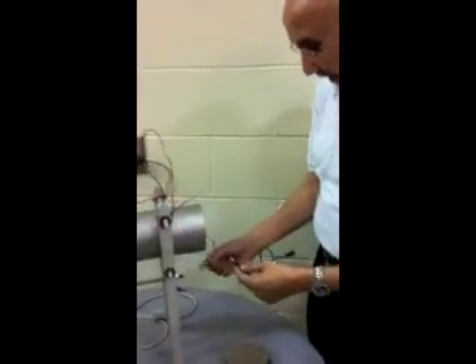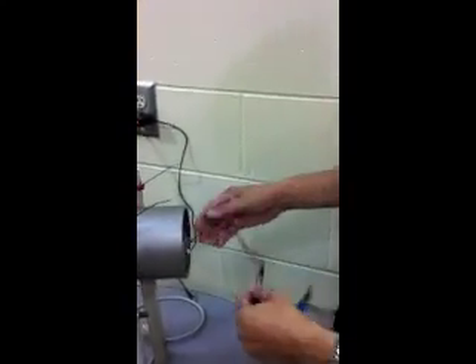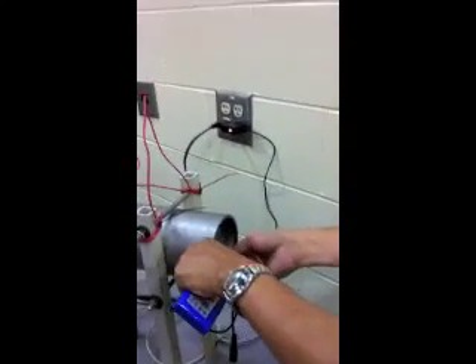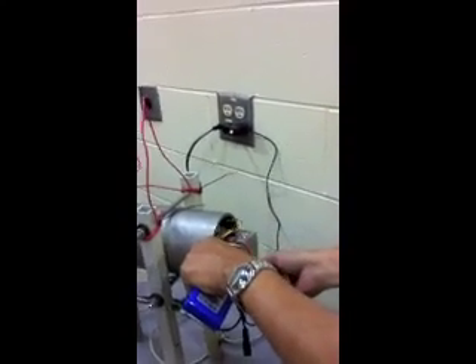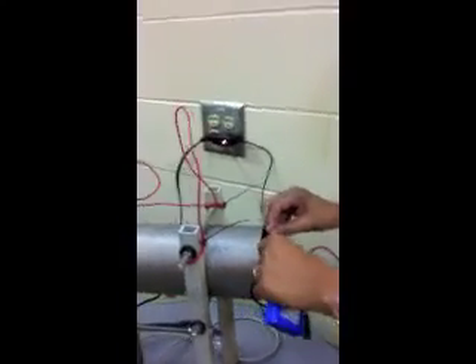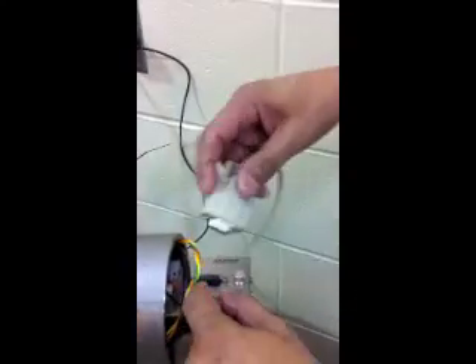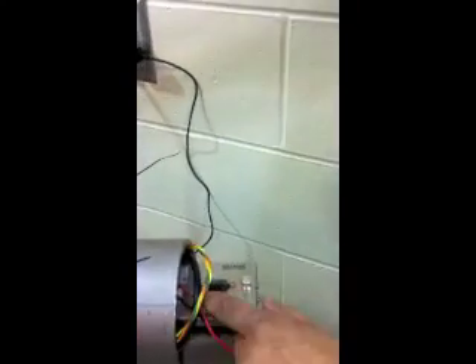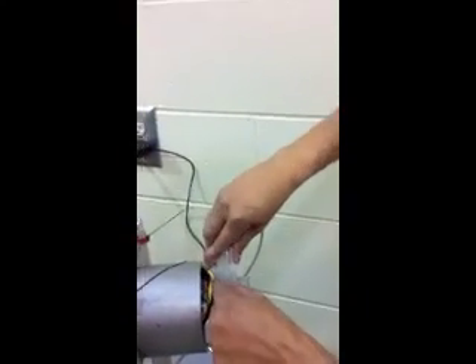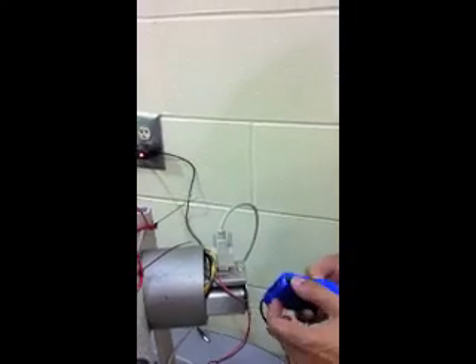Now we're going to connect this back up to the data logger. And now I'm going to pull out the data logger, and all you need to do is to pull out the data logger sufficiently to expose the serial I/O port, and to the I/O port we will then connect up a cable from the laptop, which we will be providing you. And once we've done that, we are now ready to actually start loading the program.